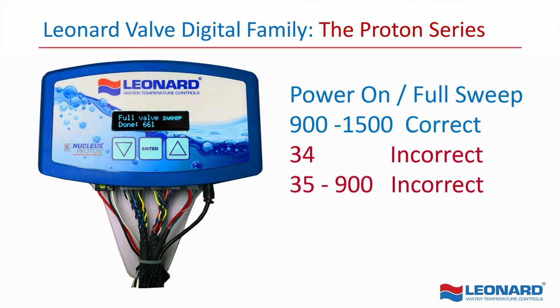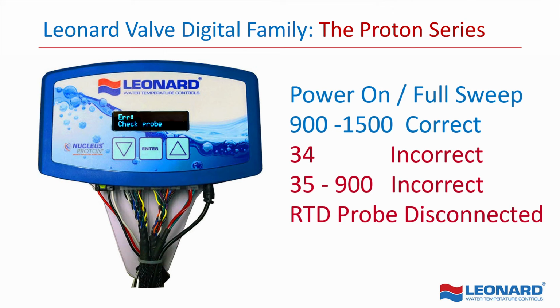If the number is between 35 and 900, that means the valve is dirty and needs to be cleaned. If you get an error for an RTD probe disconnected, that means as well that the connections are not made properly between the valve and the box for the RTD.